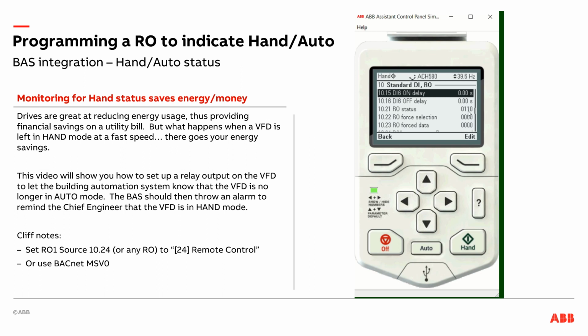And you can see my relay right there, 0, 1, 0. When I go to auto, that last 0 right there, that's relay output number 1, the one on the far right here, just toggled. So it's letting me know, hey, now I'm in auto mode. But if I go here, now that relay is toggling in 0.